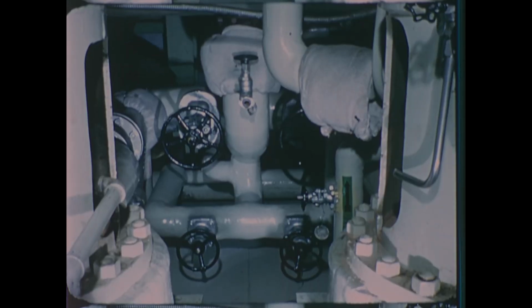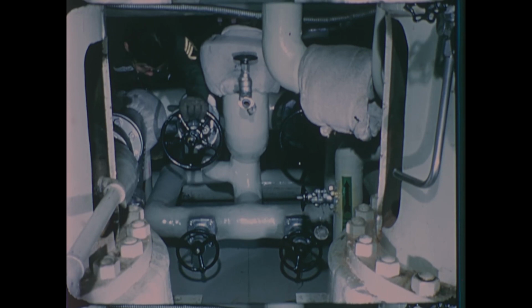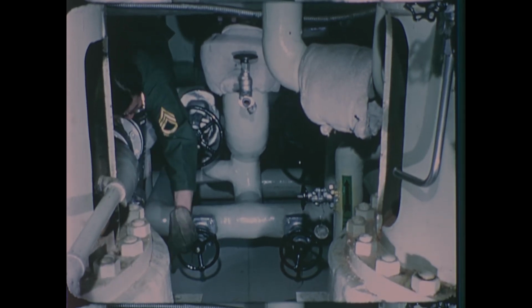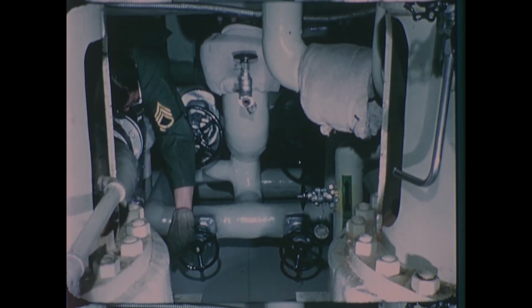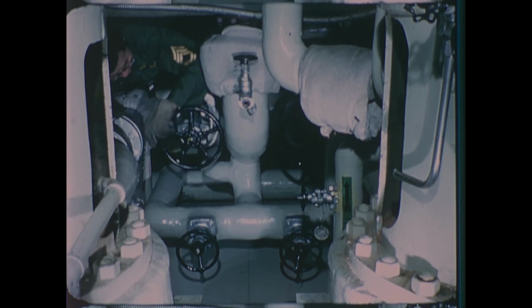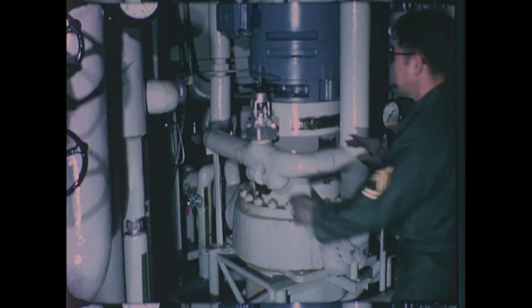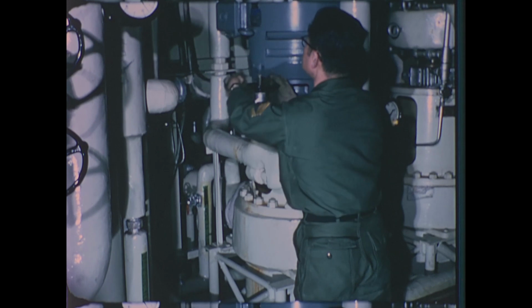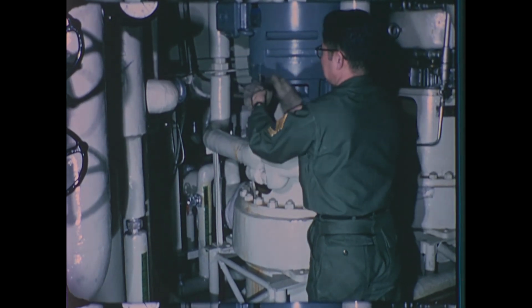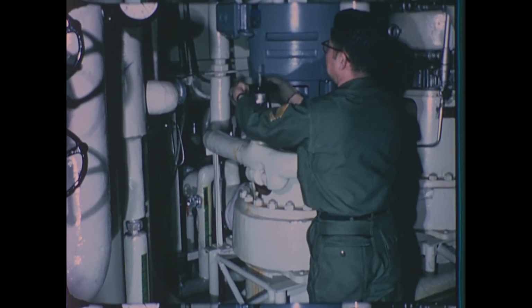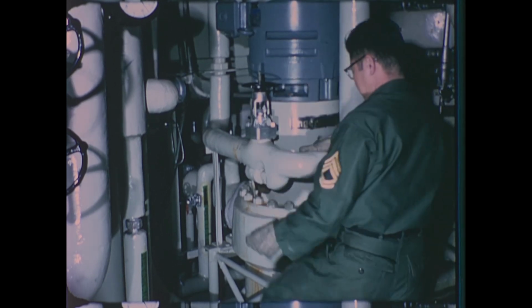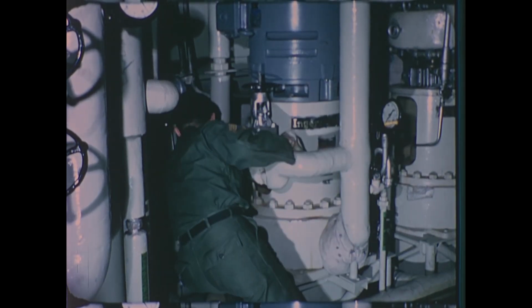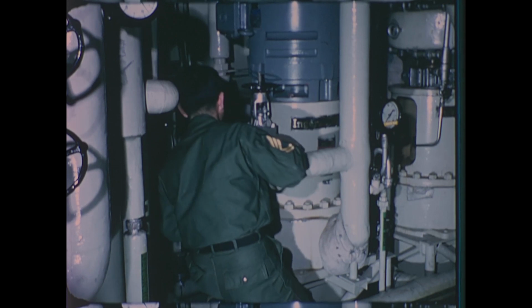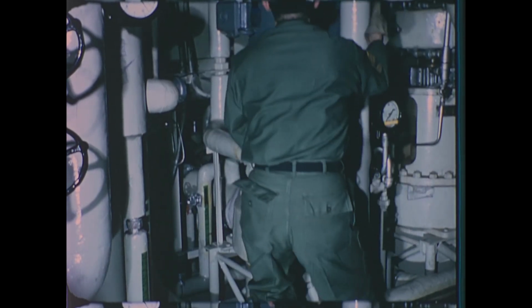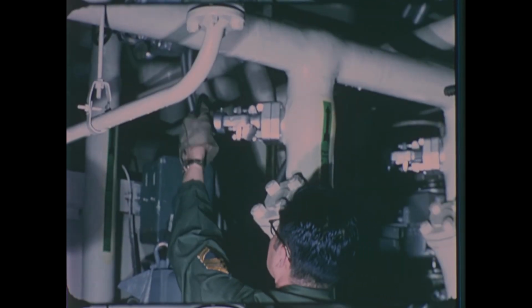Lining up the feed water system begins with opening the suction valve to the feed water pump from the deaerator tank. Next, the operator will open the minimum flow line returning to the deaerator tank. Check the valve on the anti-flash line to the feed water pump suction, and check the discharge valve from the pump.